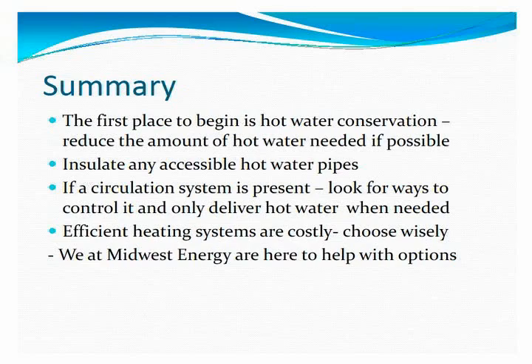So the conclusion on this sort of system is the first place to begin is hot water conservation. Choose appliances that use less hot water. Some cities even give rebates — the City of Hayes, for example, has a rebate program for high efficiency laundry equipment and so forth. Water heaters may be available that are much more efficient than before. Insulate any accessible hot water piping. If you have an unfinished basement ceiling, whatever hot water piping is visibly available and accessible, wrap some insulation on it. If you have a circulation system, look for ways to control it, such as the Taco Demand or Metlund Demand system, or the Chili Pepper, or one of the other models. Efficient heating systems are very costly though, so choose wisely. And we at Midwest Energy are here to help you make those decision options.